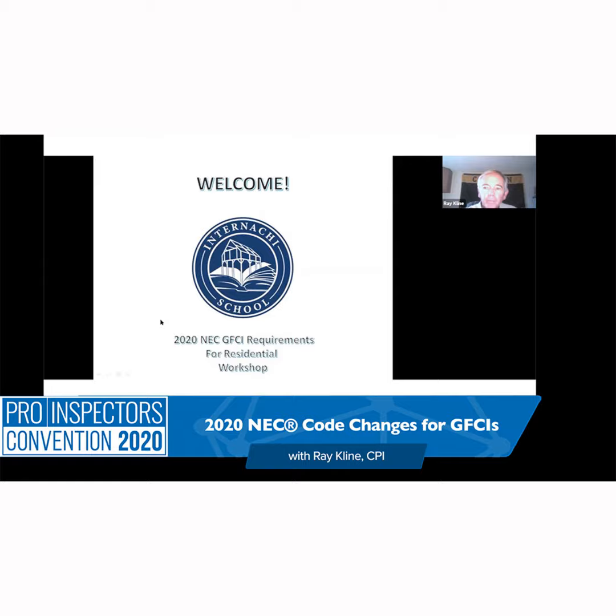A GFCI is specifically designed to protect people against electric shock from electrical systems, and it monitors the imbalance of current between the ungrounded hot and the grounded neutral conductor of any circuit. Don't let the name confuse you. These devices will operate on a circuit that does not have an equipment grounding conductor, which means that we can use these to help ungrounded homes become safer.